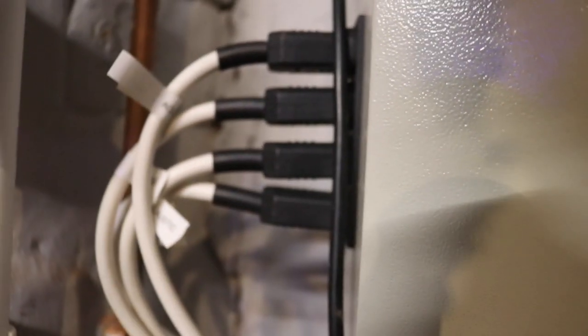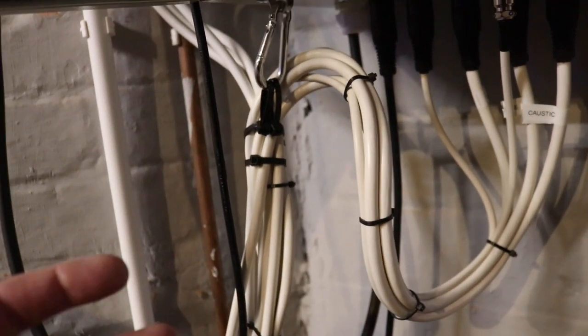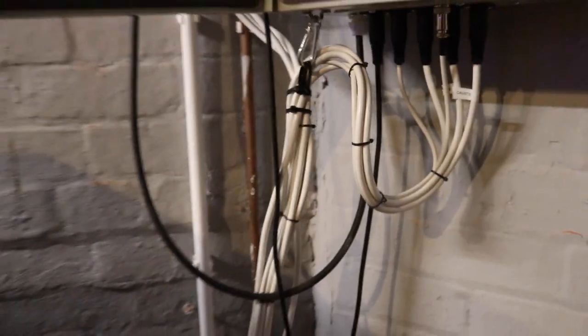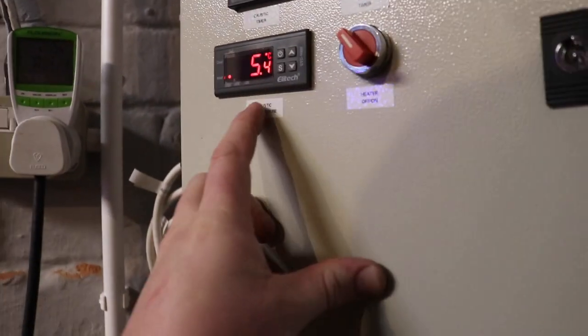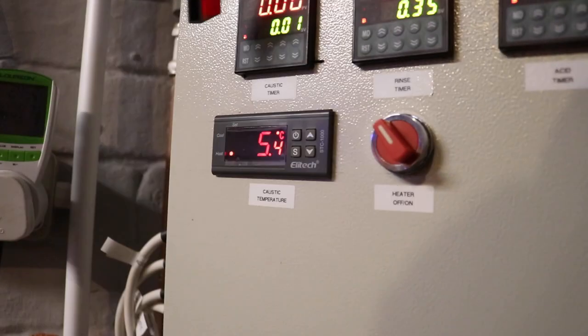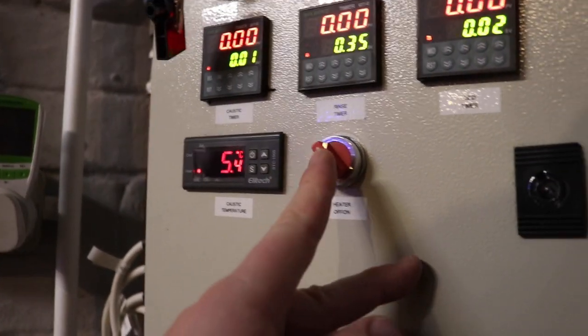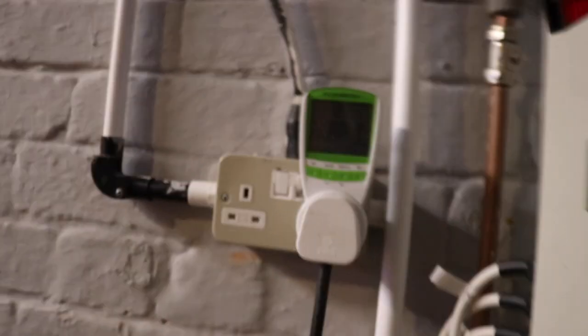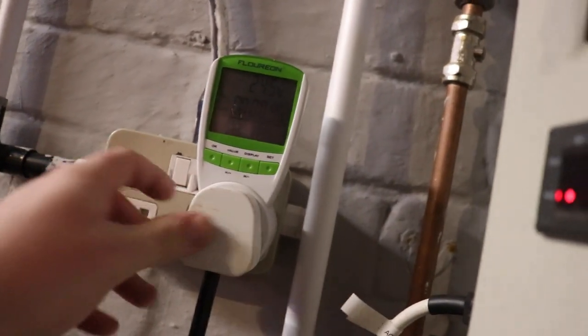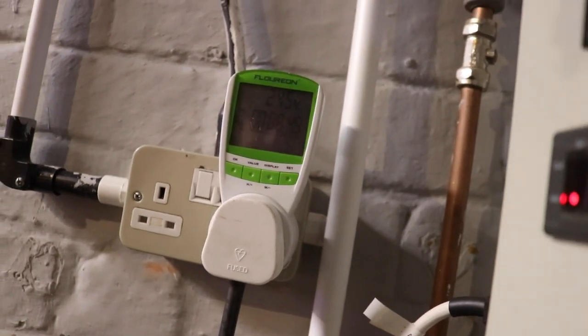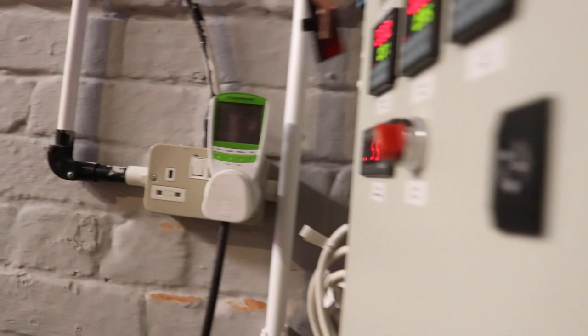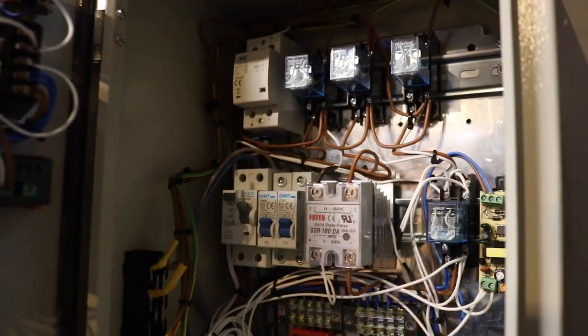Then we've used these XLR connectors to go and send our signals out to all of the on tank safety mechanisms, switching mechanisms. So all these are all low voltage, we've still got no 240 coming across here and these all operate the pumps independently when it's all geared up. On the side we've got these C13 plugs and they're carrying the power out to the pumps and the heating element. So everything that comes out of this machine is detachable so we can take the cask washer away if we have to and do any repairs on it. Then of course we've got caustic temperature, little probe under here feeding the temp probe to the STC. We've just extended the cable there and then a heater on and off switch which breaks the signal to that heater relay just there.